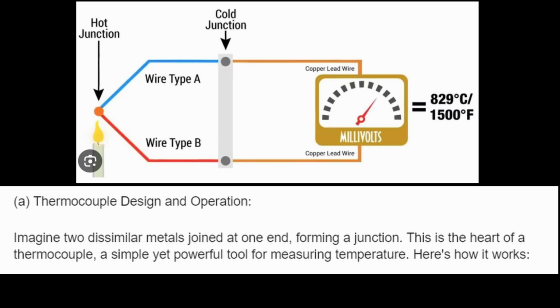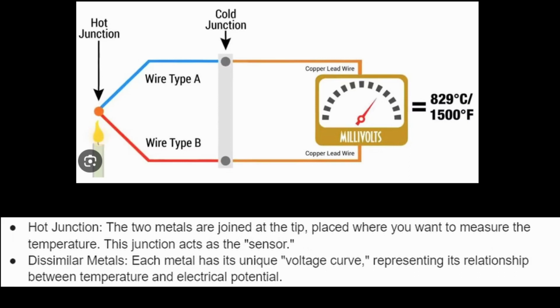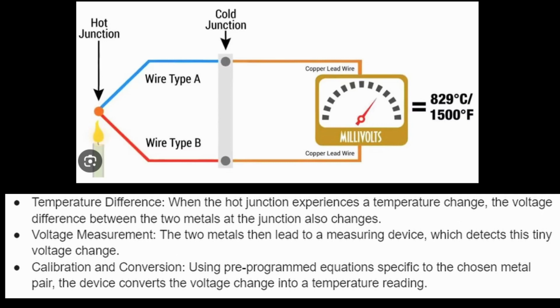Here's how it works. Look at the sketch. Hot junction. The two metals are joined at the tip, placed where you want to measure the temperature. This junction acts as the sensor. Dissimilar metals. Each metal has its unique voltage curve, representing its relationship between temperature and electrical potential. Temperature difference. When the hot junction experiences a temperature change, the voltage difference between the two metals at the junction also changes.